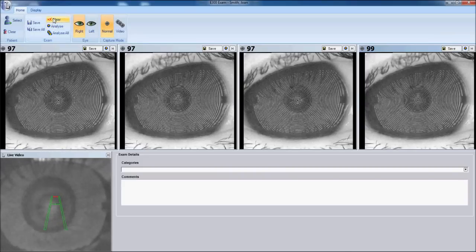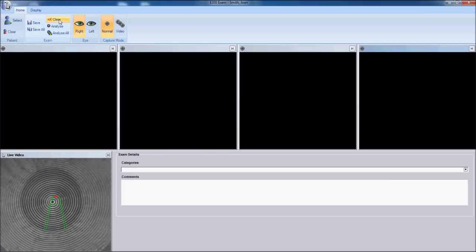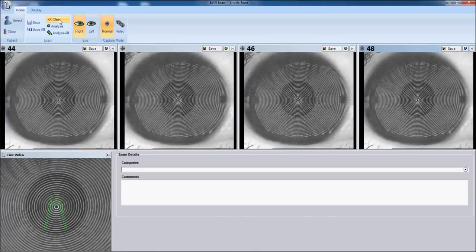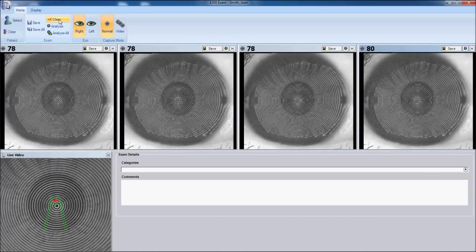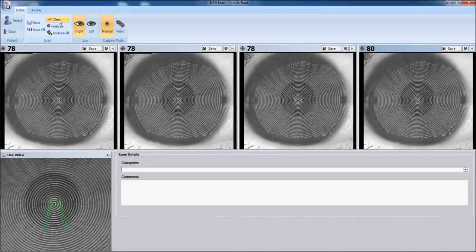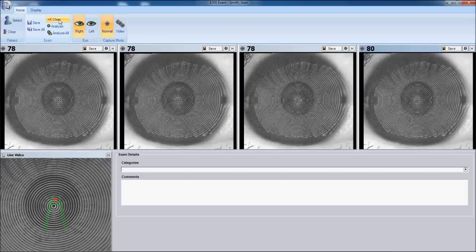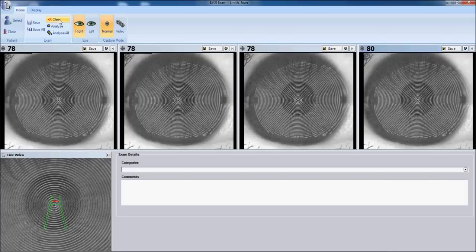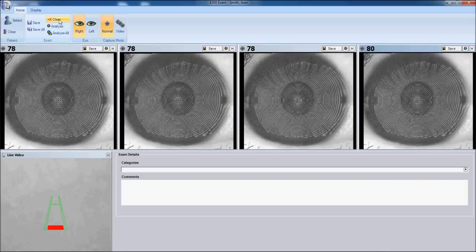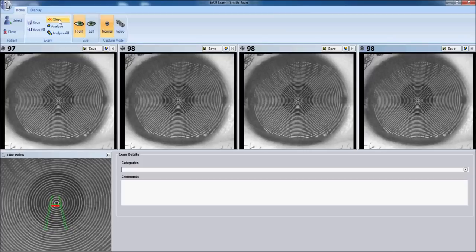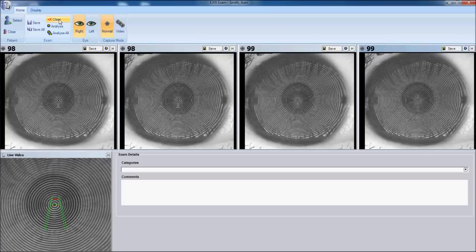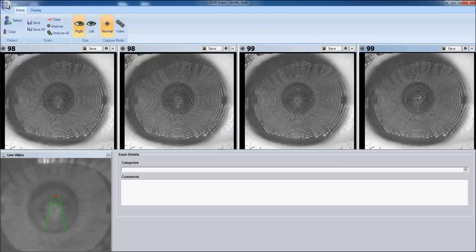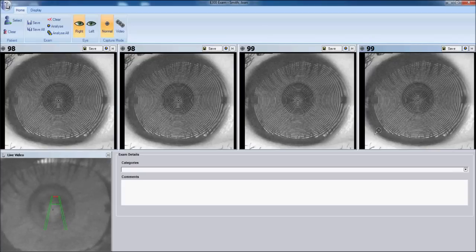Let's clear these images by clicking on the clear button. And go back in. Ask our patient to open up wide. Center the green crosshair to the apex ring. Look at the red distance indicator. Moving the instrument closer or farther away. Ask our patient to blink just prior to centering the instrument. If the placido looks like it is reflecting parallel and even we will go in. Notice we have 98% up to 99%.